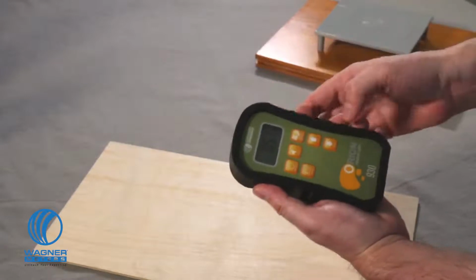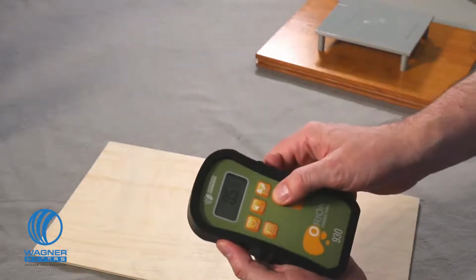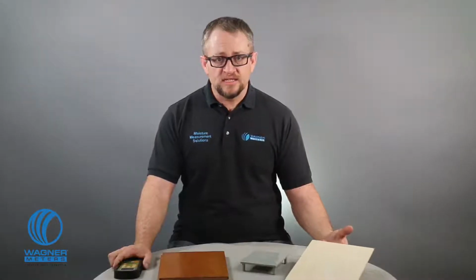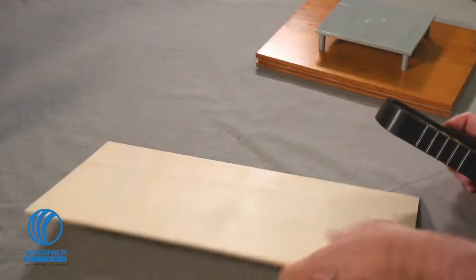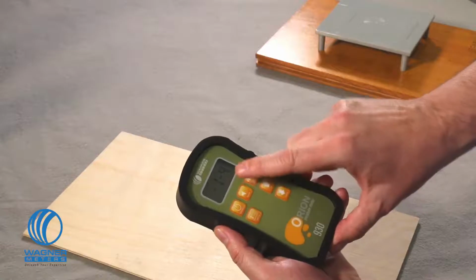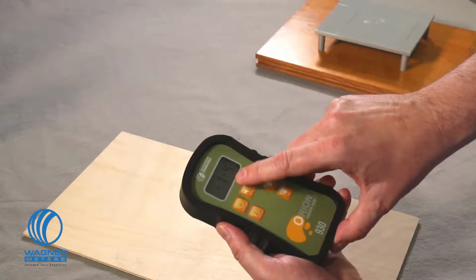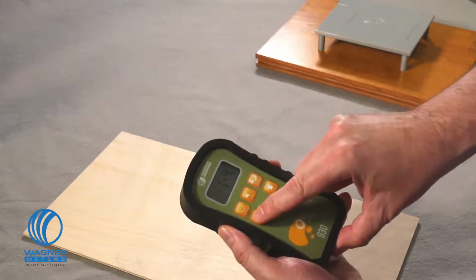I press the on-hold button to power the meter on. Then I press the species material button and use the up or down buttons to adjust the setting to 68. Since this is a thin piece, I obviously don't want to measure past the material, so I press the depth button to engage the shallow reading 1/4 inch mode. Now I'm ready to take a reading.